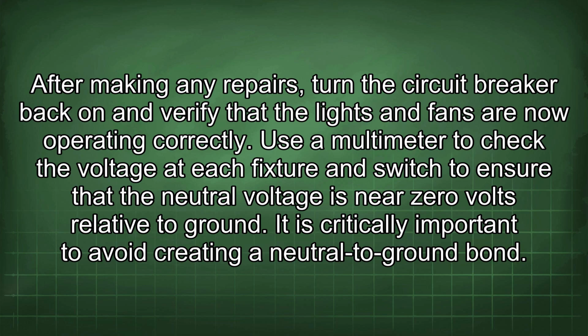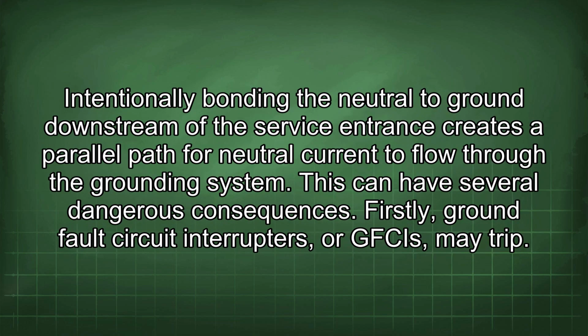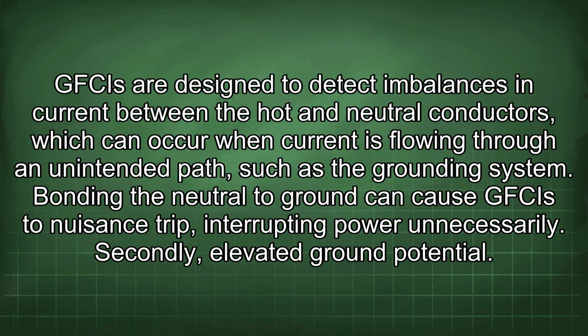It is critically important to avoid creating a neutral to ground bond. Intentionally bonding the neutral to ground downstream of the service entrance creates a parallel path for neutral current to flow through the grounding system. This can have several dangerous consequences. Firstly, ground fault circuit interrupters, or GFCIs, may trip. GFCIs are designed to detect imbalances in current between the hot and neutral conductors, which can occur when current is flowing through an unintended path, such as the grounding system. Bonding the neutral to ground can cause GFCIs to nuisance trip, interrupting power unnecessarily.